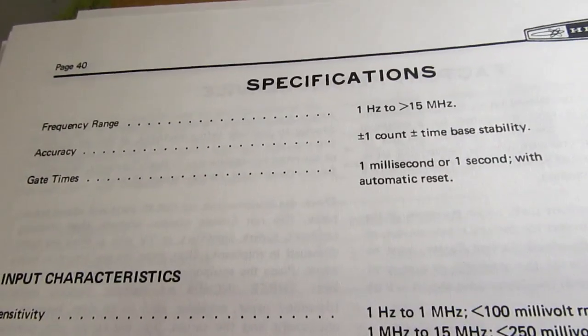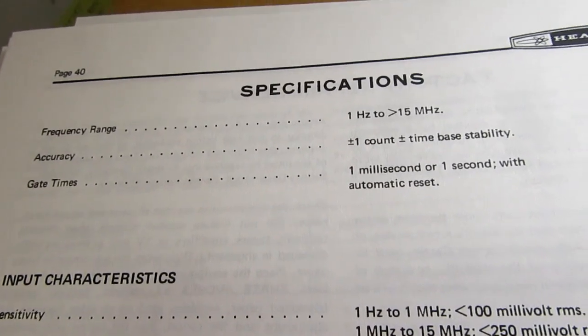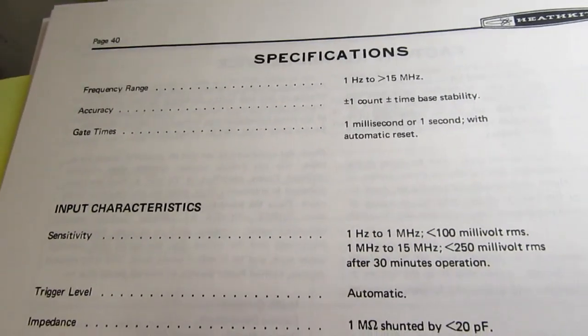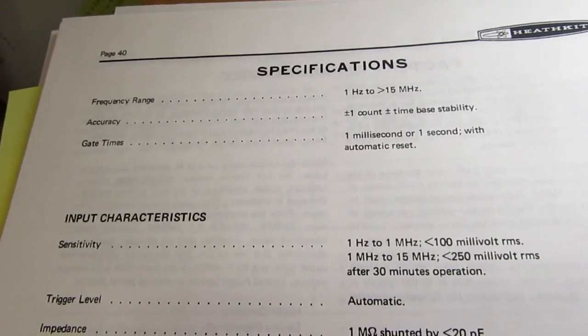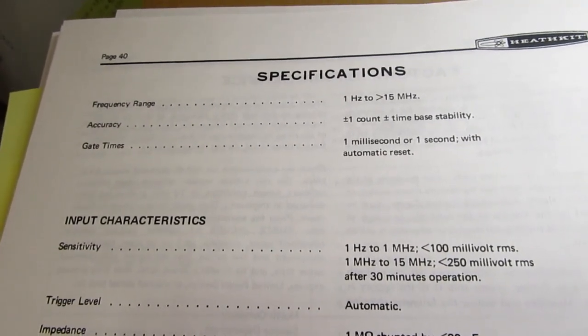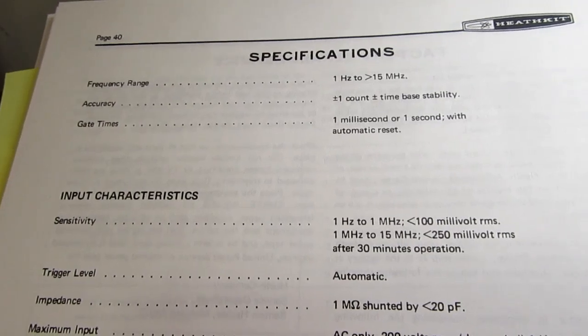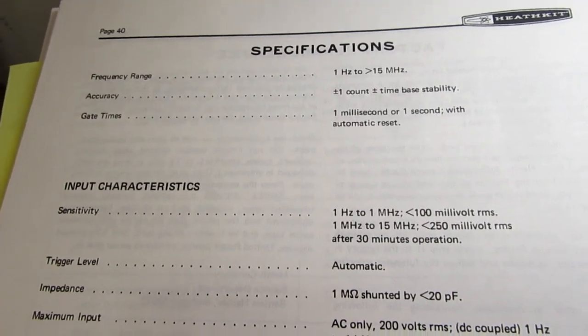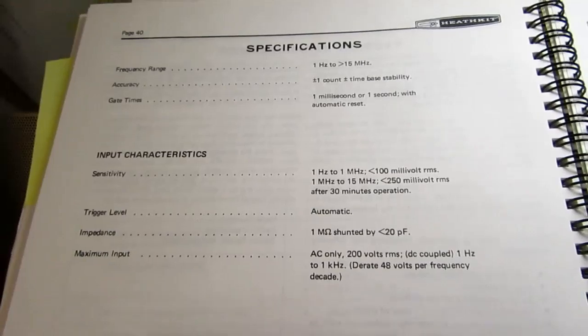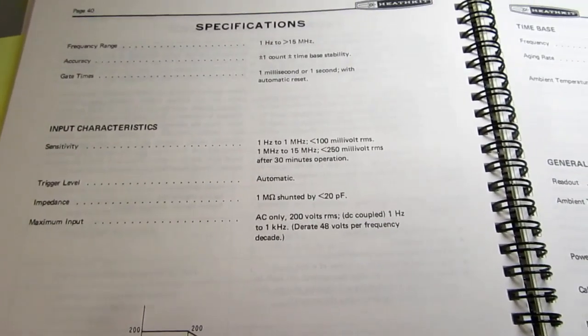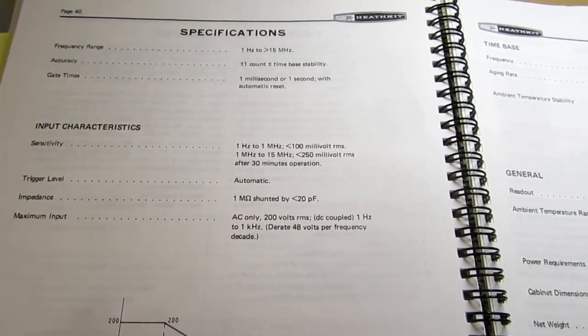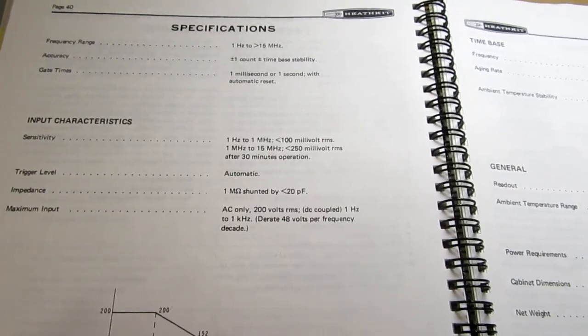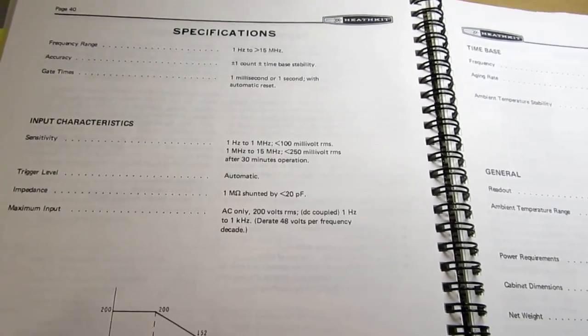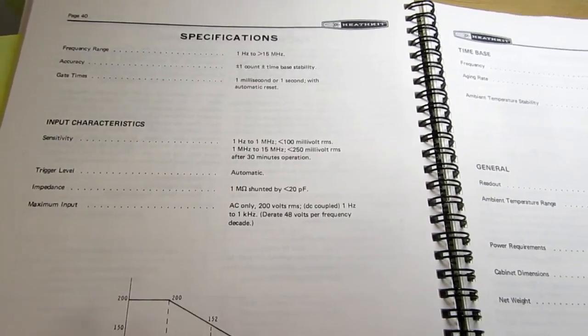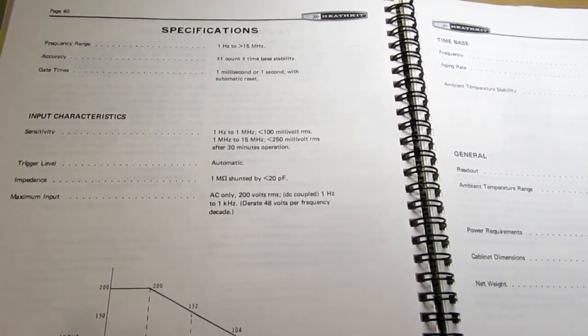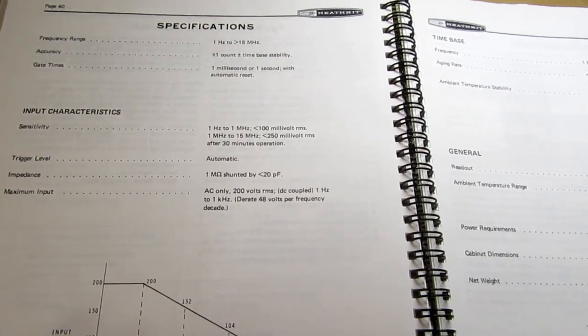1 Hertz to 15 megahertz minimum. It can go higher potentially. Accuracy is plus or minus 1 count, plus or minus the time base stability. Gate times are either 1 millisecond or 1 second with automatic reset. Sensitivity from 1 Hertz to 1 megahertz is less than 100 millivolts RMS. 1 megahertz to 15 megahertz, less than 250 millivolts RMS. Trigger level automatic. Impedance is 1 mega ohm shunted by less than 20 picofarads.